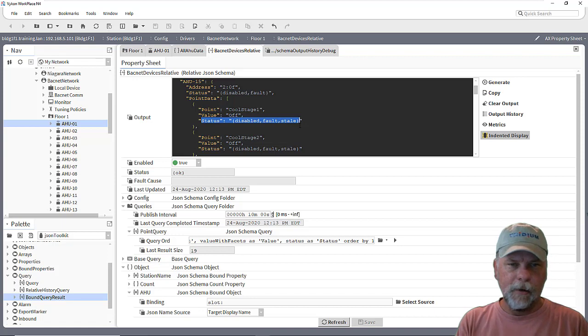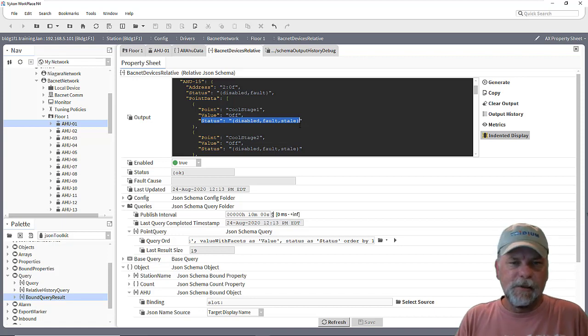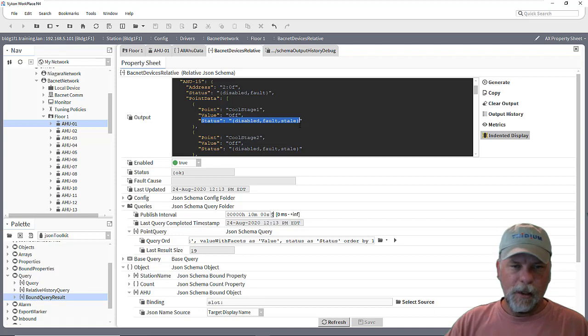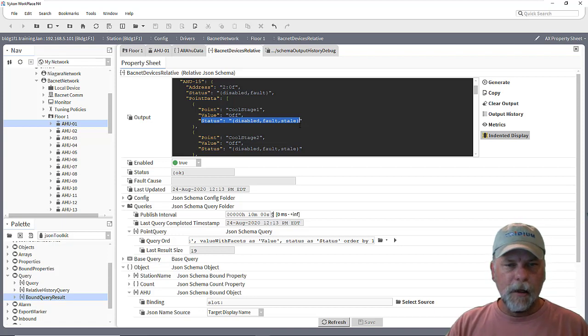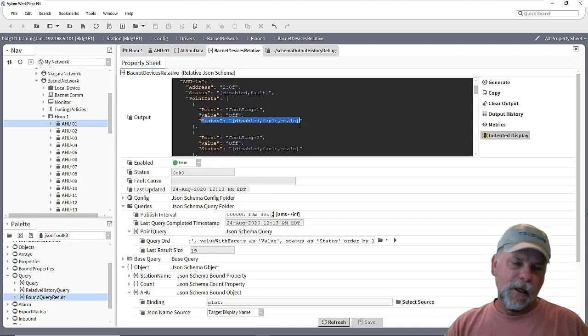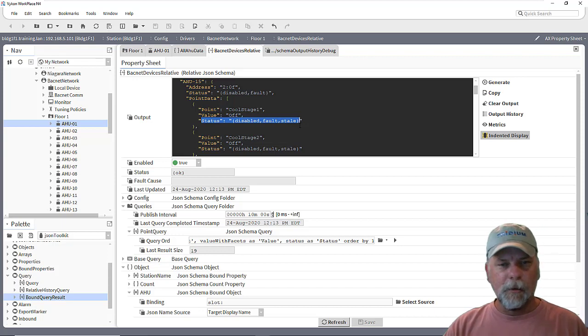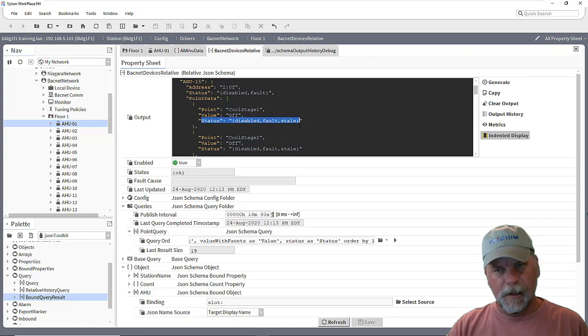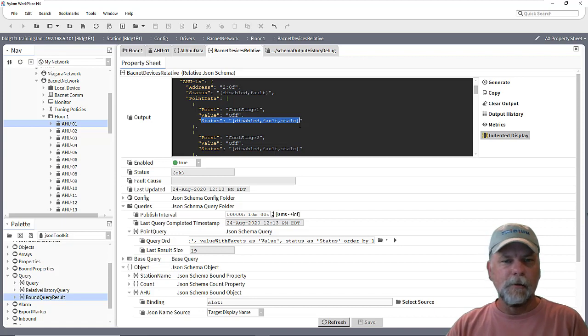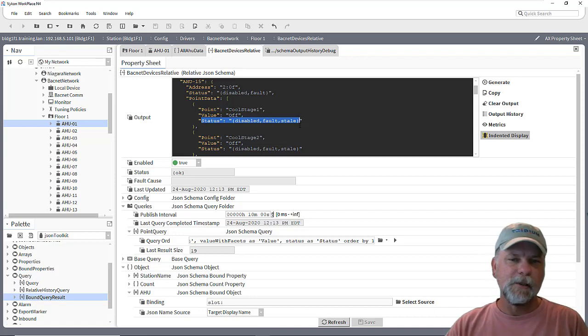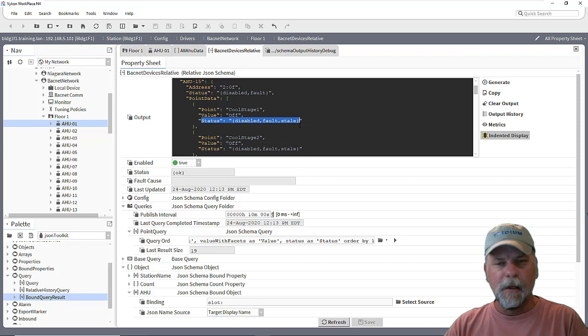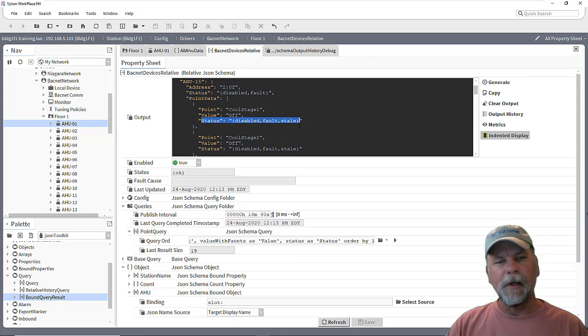And for each one of those output messages it'll include the data for that particular AirHandler device. So it lets us get a little more granular about a message instead of one big message with all the point data. Now we're going to take a pause here and we'll pick back up with the next part and we'll talk about how do I link this relative JSON schema then out to MQTT points to publish them. And there's a couple different ways we can go about doing that as well. So stay tuned to the next part. Thanks.